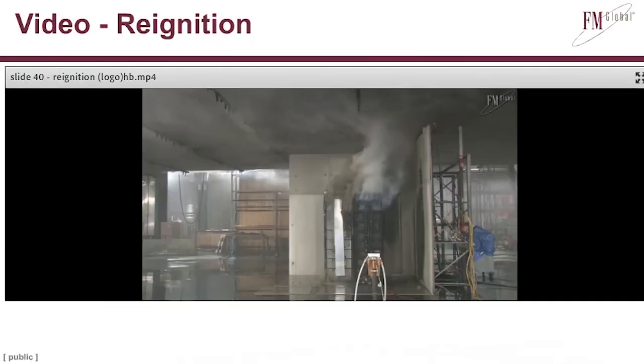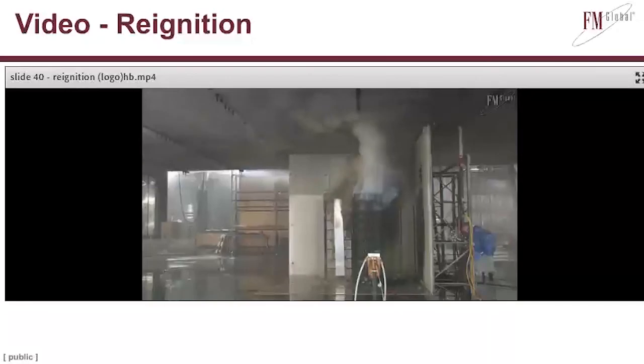And if we can pull the video down now, we'll take a look at what we saw. And so what we saw was that the temperatures in the rack, we have data to show this, in the main rack, the one on the right, were actually still increasing. And you can see this white smoke that's exiting. In fact, the velocity of that smoke started to increase over time.